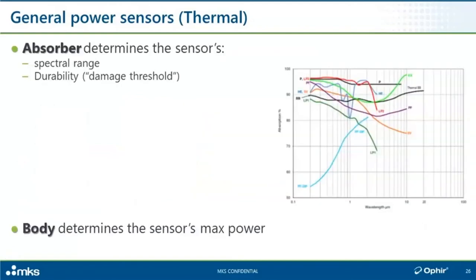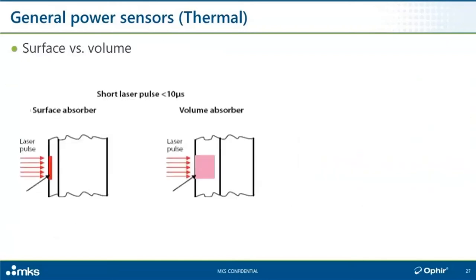The absorber used in a given sensor determines the spectral range of the sensor. As mentioned, different materials absorb different wavelengths differently, and also the durability — a given sensor material can handle a given maximum power density or energy density. We have spectral relative sensitivity curves for different sensors and absorber types on our website, in the catalog, and in the data sheets. The body of the sensor determines the maximum power for which it can be rated, because different sensor bodies dissipate heat faster or slower.